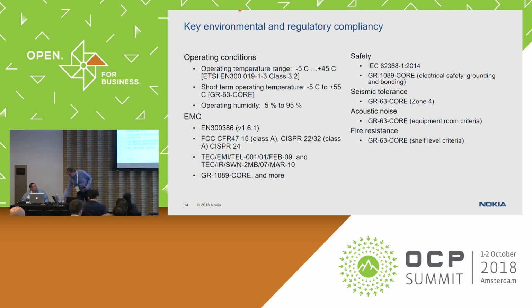Okay, just a quick summary of the environmental and regulatory compliance. We do support temperatures up to plus 45, and short-term exceptional situations up to 55, and of course the normal EMC and safety requirements, and also we are aiming at full NEBS compliance for this unit.